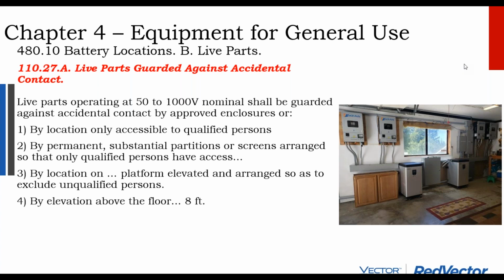If it has exposed terminals, you're going to run into different design considerations than if those terminals are enclosed in a case that's provided by the manufacturer. So if you do have exposed terminals on your batteries, what do? Well, the location can only be accessed by qualified persons. Does that necessarily mean you have to have a locked battery room? No. It's a good idea to have a dedicated battery room that's locked, but it's also common to have a cage inside a garage that is a locked cage to prevent people from getting into the square footage of where the batteries are, but isn't necessarily a dedicated locked room.